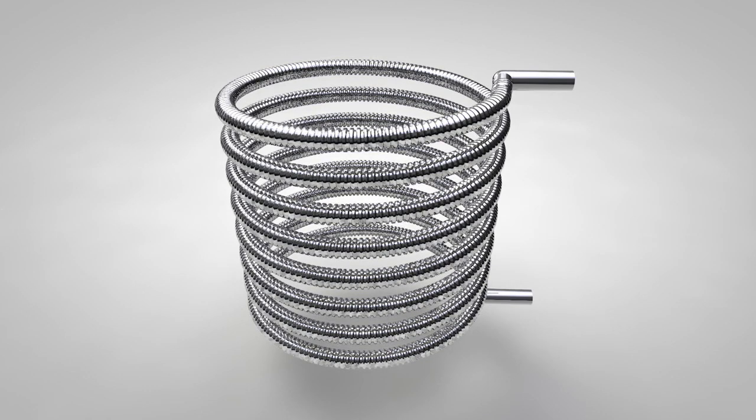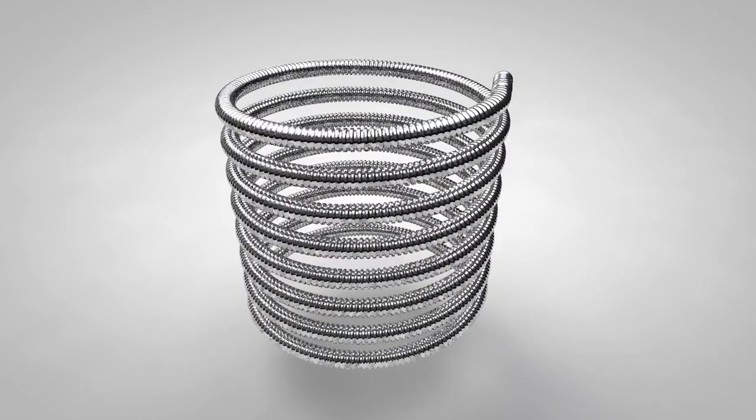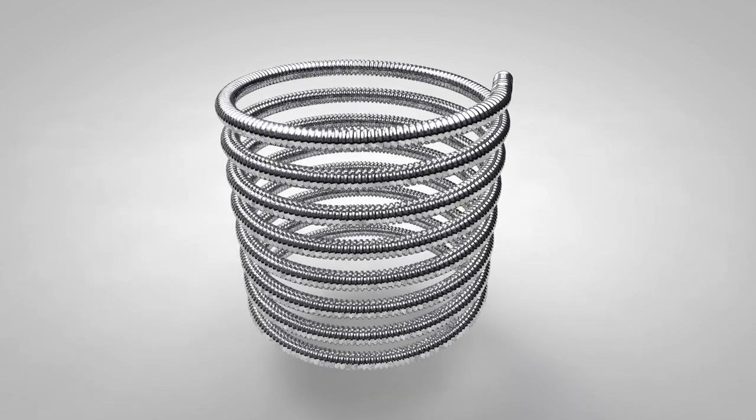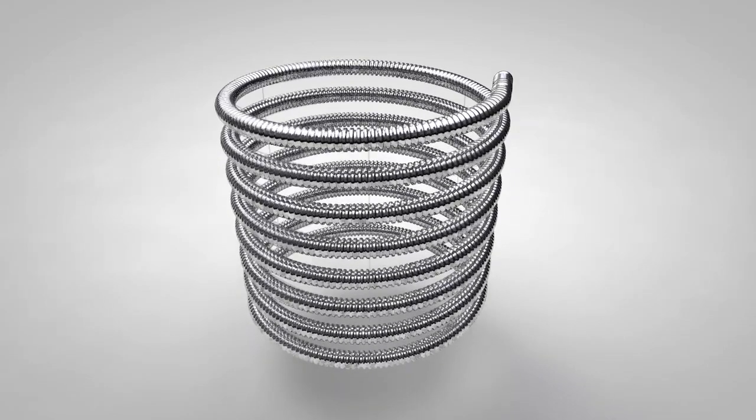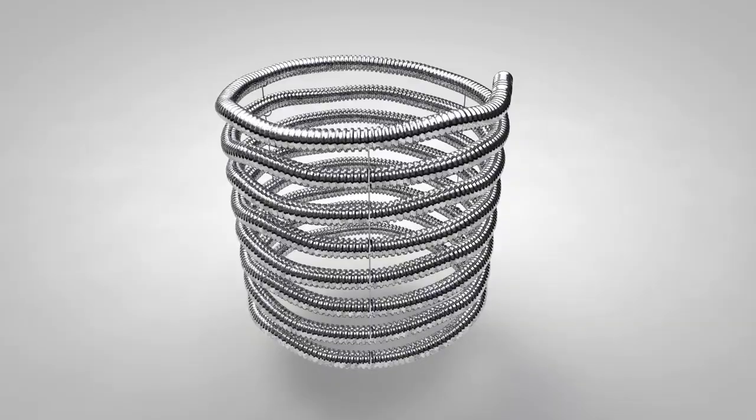3. Some manufacturers use a corrugated pipe or one with fins to increase the surface area. These pipes are very flexible and provide a solution where very large surface areas are needed, such as for a thermal store. However, the pipe is intrinsically flimsy and will shake about inside the cylinder even when supported by clips, making the coil more prone to leaks.